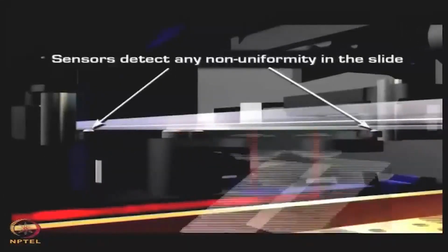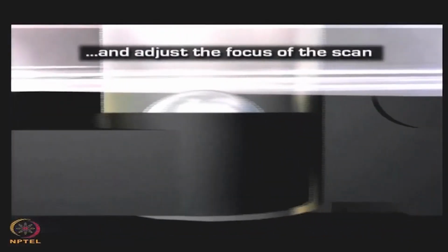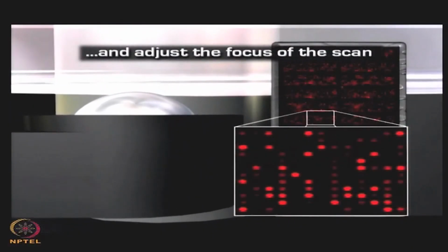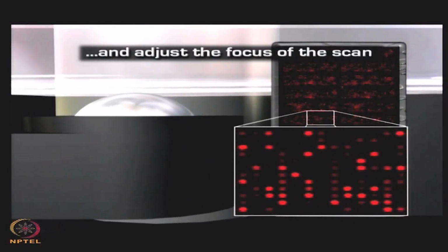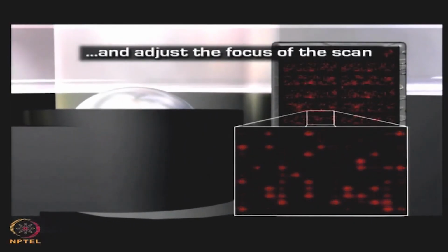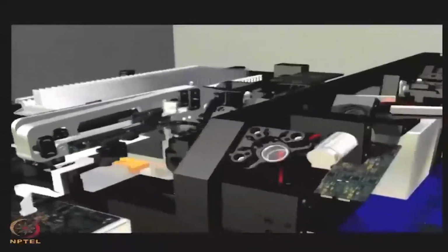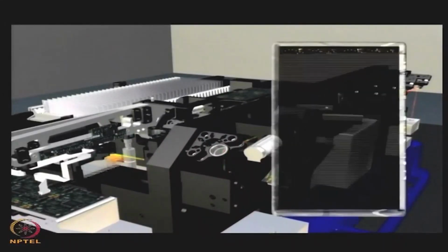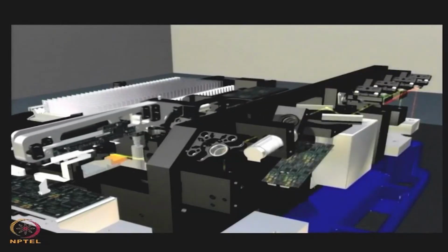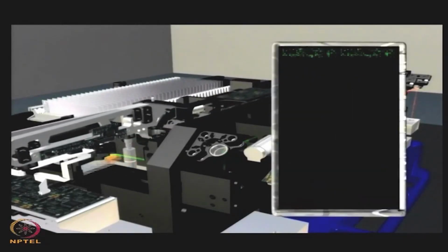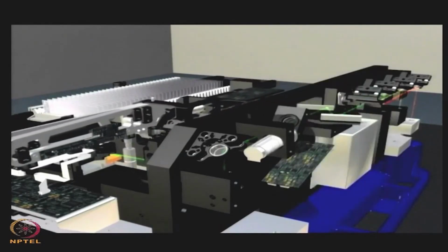As the scan proceeds, sensors detect any non-uniformity in the slide surface, and the robotic arm adjusts the slide position accordingly to ensure the array surface is always in perfect focus. Each channel is scanned sequentially, and the developing images are displayed on the monitor. The multi-channel TIFF images are saved automatically according to file naming conventions specified by the user.